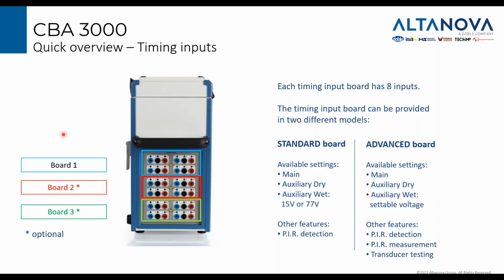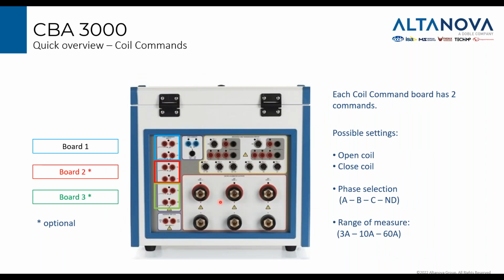We are a little bit late, so let's go fast, having a quick overview on the CBA 3000. It is provided with configurable hardware. You can have only one of these boards, so let's say up to 8 timing inputs, but it can be up to 24. And every input can be programmed by the operator, so the operator can decide the function of each one. The number of commands is also configurable, so you can have only 2 or up to 6. It is very dependent on what you need.